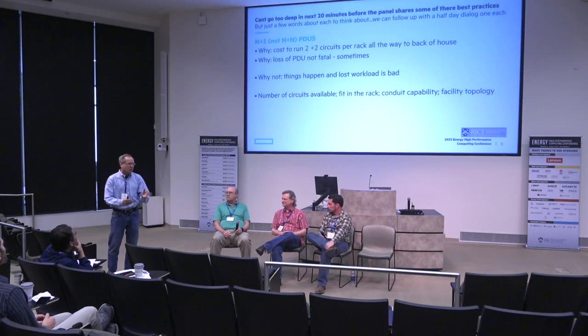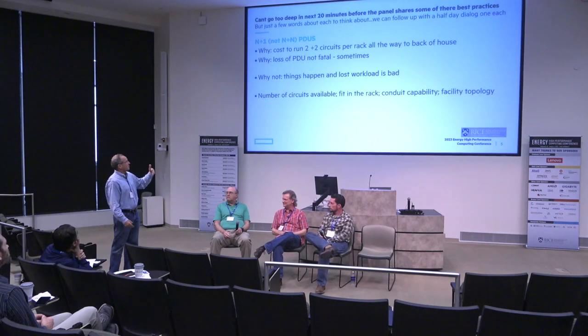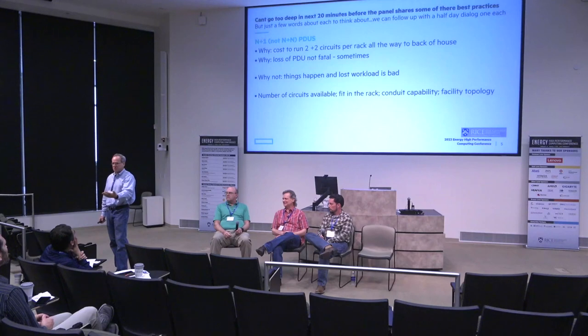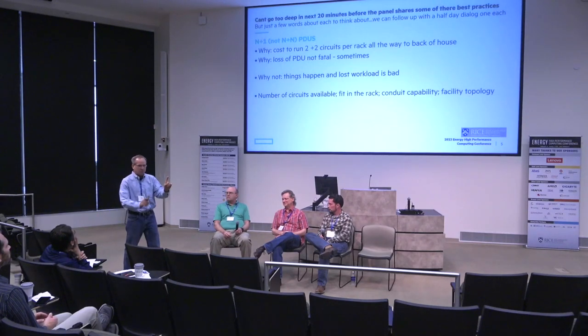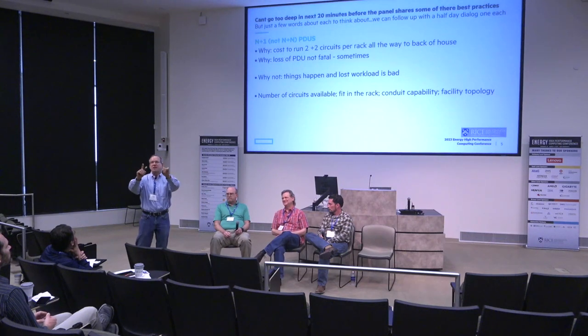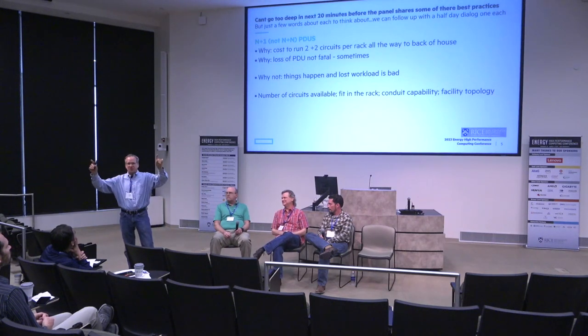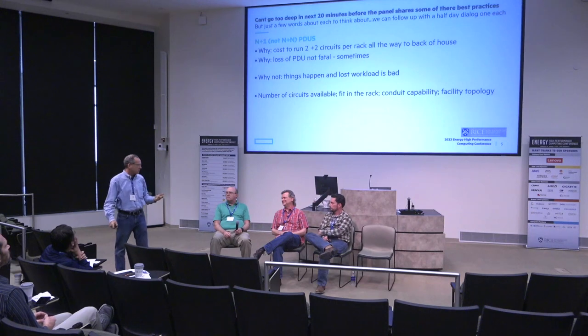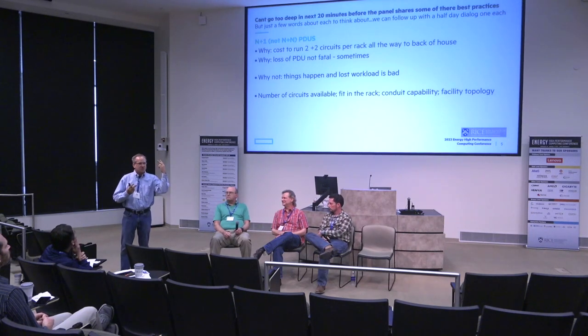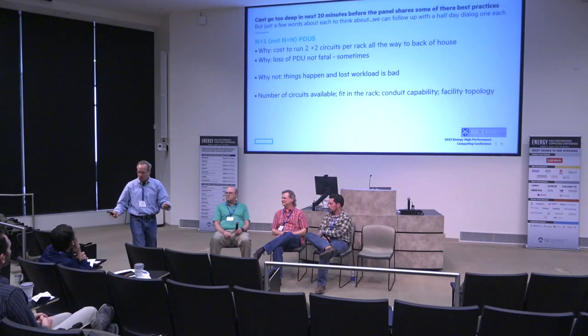And so if you've got some level of resiliency or redundancy, it's now a question of how many whips do you want to run to the rack and what's your resiliency? I think everybody was thinking, okay, it used to be I have an A whip and a B whip from my PDUs, and whether I have UPSs or other generators behind them, it really didn't matter. But now I think it was pretty easy, especially at 208, to have two A whips and two B whips. So at 208 in a colo, each whip was 17 kilowatts.